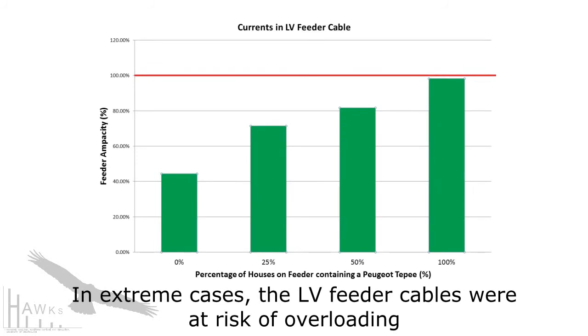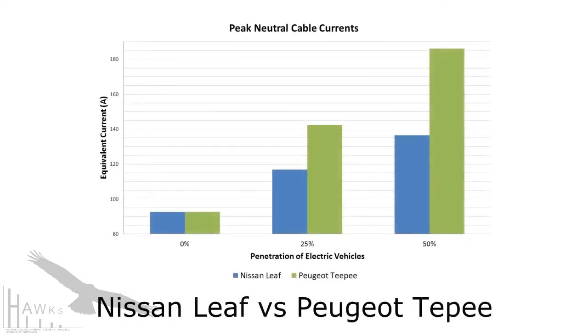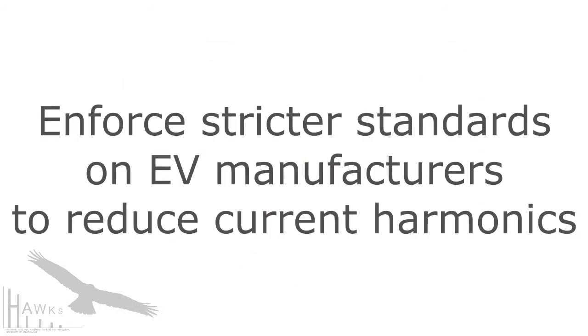When a high number of electric vehicles were introduced to the network, the low voltage feeder cables were at risk of overloading. We also found that these effects were much worse when using the Peugeot Tepee harmonic profile in place of the Nissan Leaf. We proposed that one method of reducing harmonics in a future distribution network would be to enforce stricter standards on electric vehicle manufacturers.